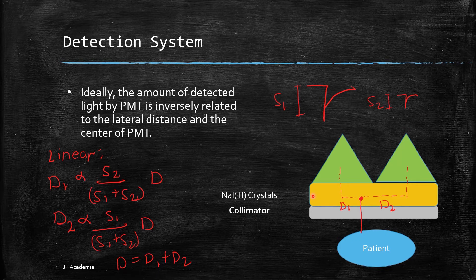Ideally, the amount of detected light by the photomultiplier tube is inversely related to the lateral distance and the center of the PMT. We also have here the signal detected by this first PMT S1, then a smaller signal here for S2. The relationship between the signal amplitude and location with respect to the PMT center would be linear.